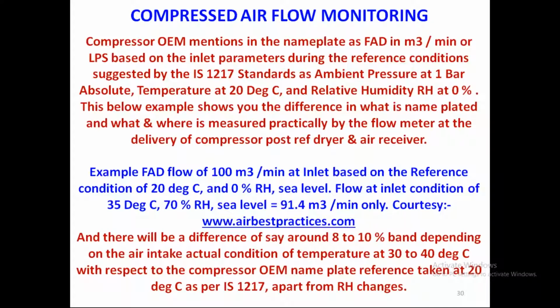They have taken the deliverable at a temperature of 20 degrees and at a relative humidity of 0%. This is not going to happen anytime. But this is the reference point at which compressor OEMs give their nameplate, say 160 kilowatt means 1000 CFM. Let us apply best practices. We have to visit the global energy management websites. A lot of inputs are available to industry, to academics, to the professors, and many of these inputs can be deployed horizontally to industry, where, for tropicalized conditions in the Indian climate, this can be adjusted for the changes happening in the ambient. The machine needs a steady input, but the cyclic changes happening in the ambient have to be matched to the steady input for the given machine.